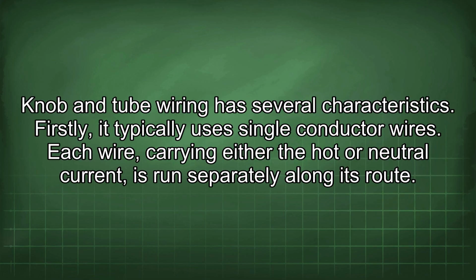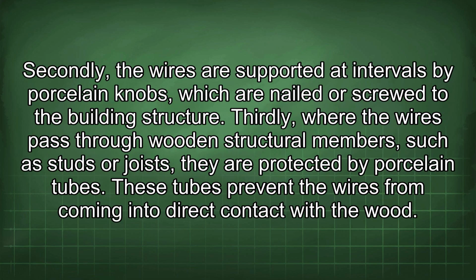Knob and tube wiring has several characteristics. Firstly, it typically uses single conductor wires. Each wire, carrying either the hot or neutral current, is run separately along its route. Secondly, the wires are supported at intervals by porcelain knobs, which are nailed or screwed to the building structure. Thirdly, where the wires pass through wooden structural members, such as studs or joists, they are protected by porcelain tubes. These tubes prevent the wires from coming into direct contact with the wood.